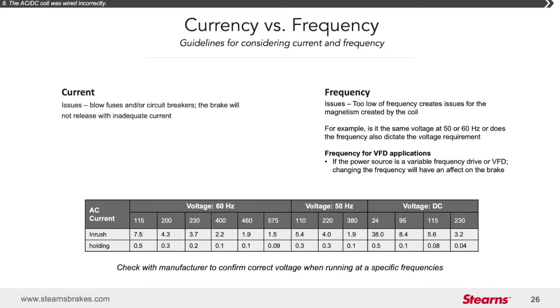Understand that the voltage requirement can change depending on the frequency. In other words, if you have a 460 volt 60 hertz coil, the same coil will only require 380 volts at 50 hertz, unless of course you have a dual frequency coil. It's important to know and understand what rated coil you have in your brake to assure long life of the coil and long life of the brake.